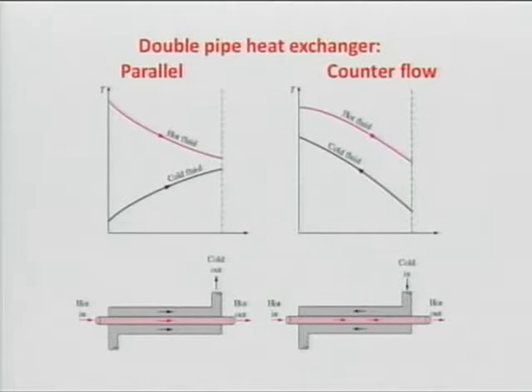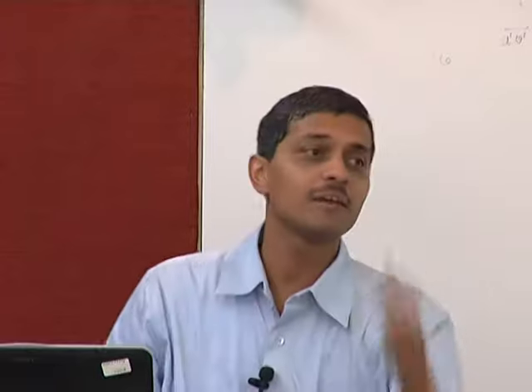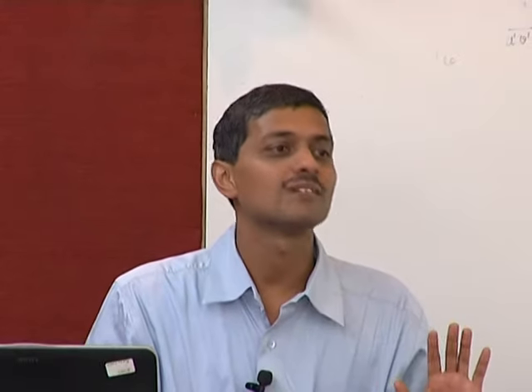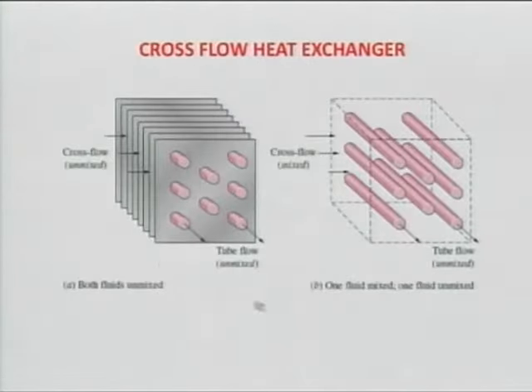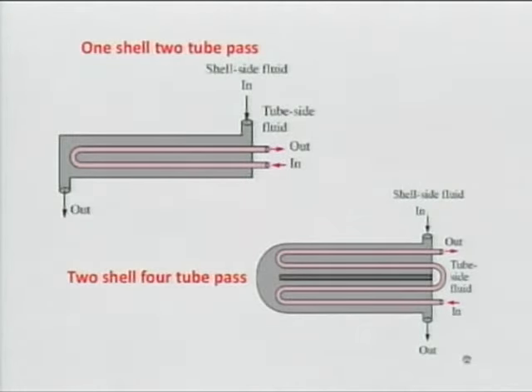It is not a standard rule. The size of a tube-in-tube heat exchanger built in the lab cannot be one pass. If the calculated length turns out to be 20 meters — that is 60 feet, or a 6-storey building — I cannot lay that down. I will have to take bends and make multiple passes, but that will increase the pressure drop. Everything comes with a cost. There is a limitation up to which you can hold a tube-in-tube heat exchanger.